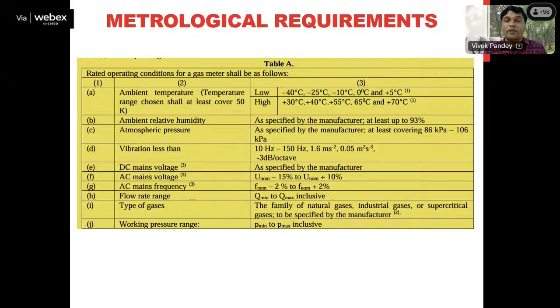Now, there is one thing: whenever a manufacturer is specifying a temperature range, from minimum to maximum, as I gave you in the previous slide, he cannot select just any combination. Suppose, from the table, a range of minus 10 degrees Celsius to 30 degrees Celsius. Minus 10 degrees Celsius is the lower temperature and the maximum is 30 degrees Celsius. No, it is not allowed, because our rule says that a minimum gap of 50 degrees Celsius should be there. So if he decides the lower temperature as minus 10 degrees Celsius, he can go for 40, 55, 65, or 70 degrees Celsius. He cannot choose the higher temperature as 30 degrees Celsius. Fine, so these are also defined in our regulations.